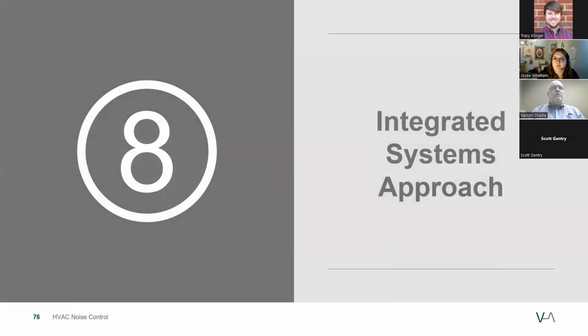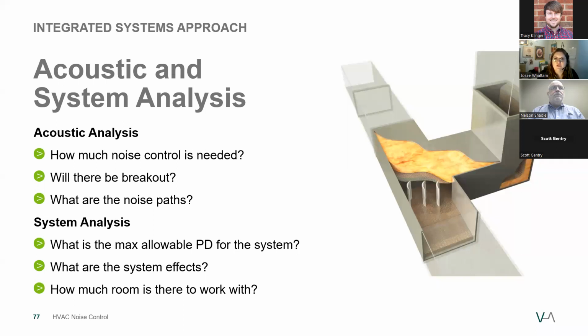Okay, this brings us back to the right approach to noise control, the integrated systems approach. It's where the system is analyzed so that the appropriate solution can be designed into the project, reducing the risk of a noise problem after the building is built. It starts with the acoustic analysis, which addresses how much noise attenuation is needed, where the breakout might happen, and all potential noise paths. Then the system analysis looks at the max allowable pressure drop from the system, what the potential system effects are, and how much room there is to work with. This process identifies the acoustic needs and system requirements for a specific application so that we can develop the right solution for the job.